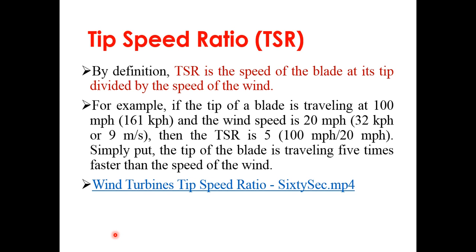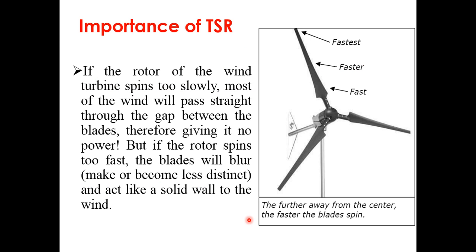The tip speed ratio is the speed of the blade at its tip divided by the wind speed. For example, if the tip of the blade is traveling at 100 miles per hour and the wind speed is 20 miles per hour — approximately 32 km/h or 9 m/s — then the TSR is simply 100 divided by 20, which equals 5. The blade tip is traveling five times faster than the wind speed.